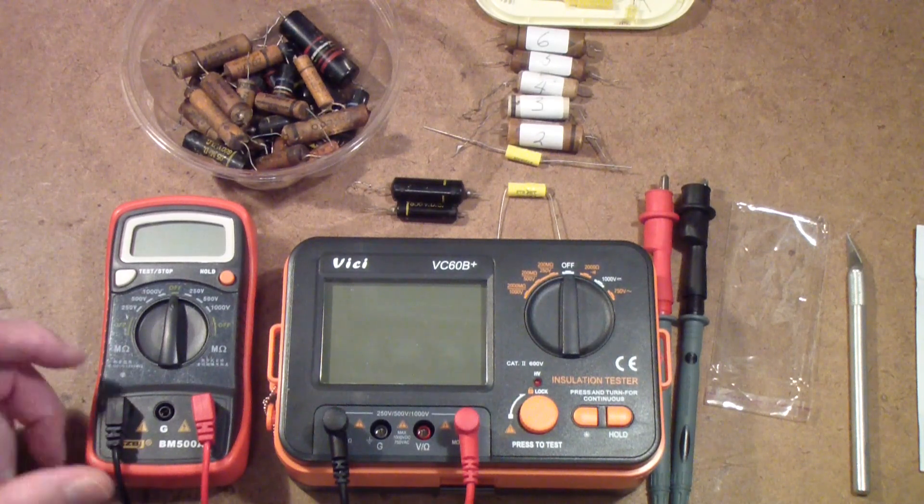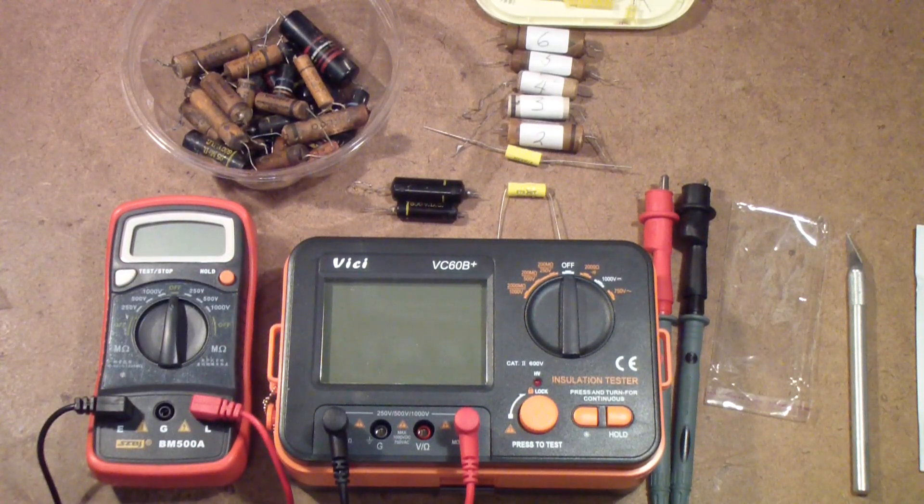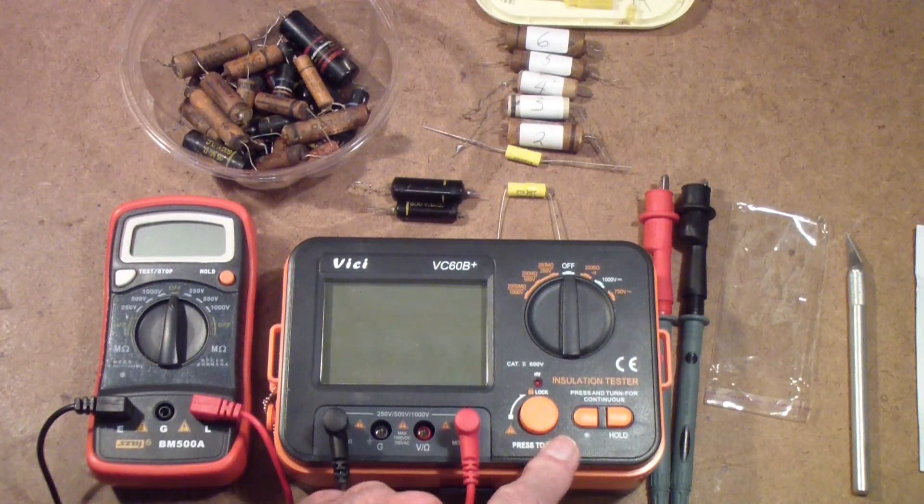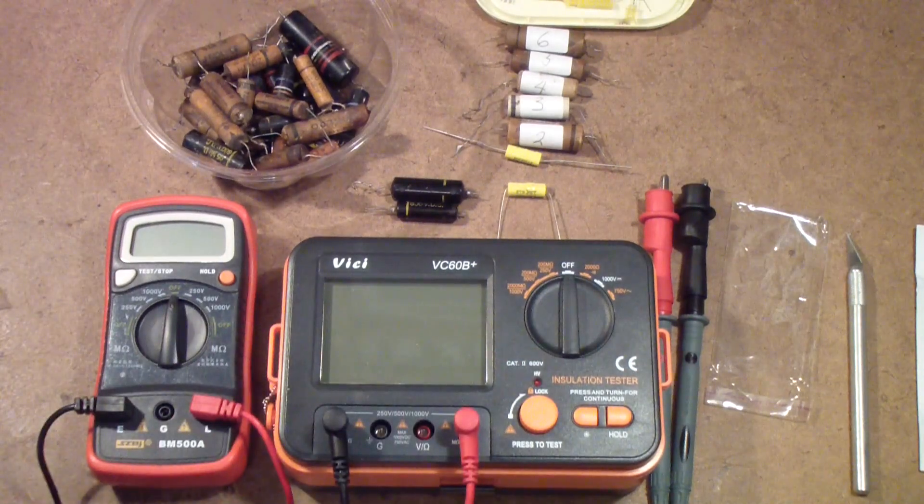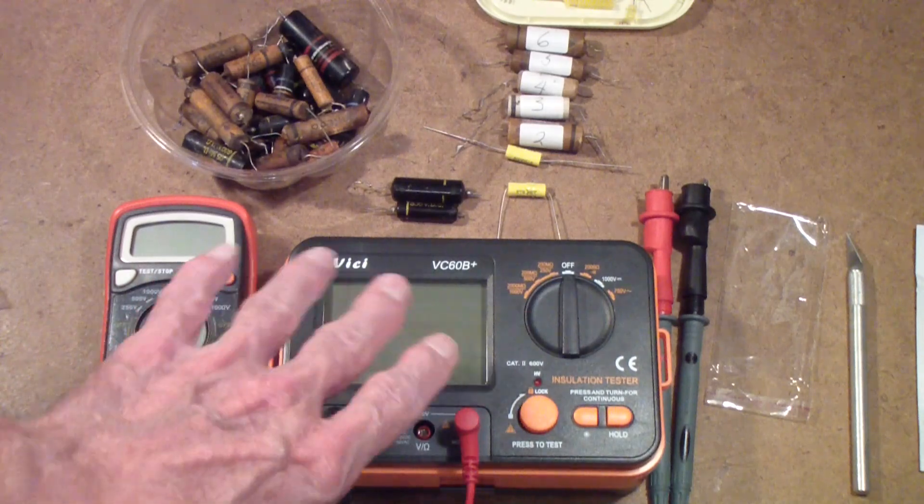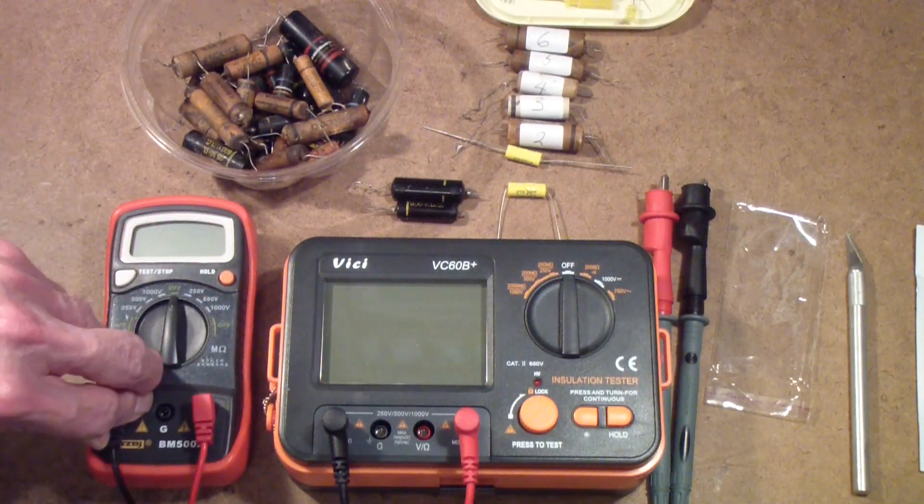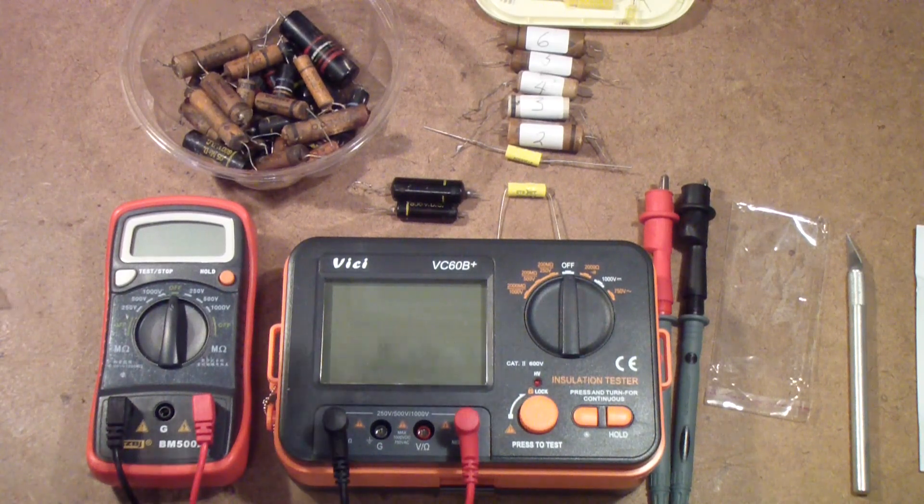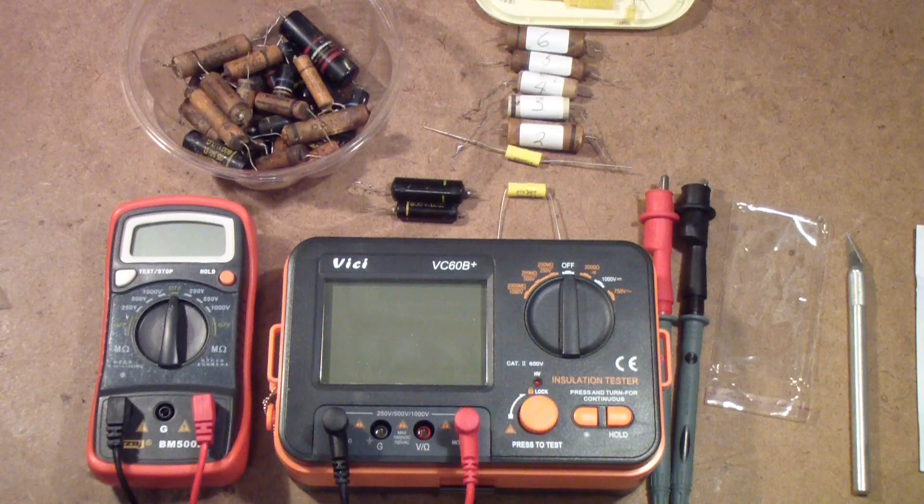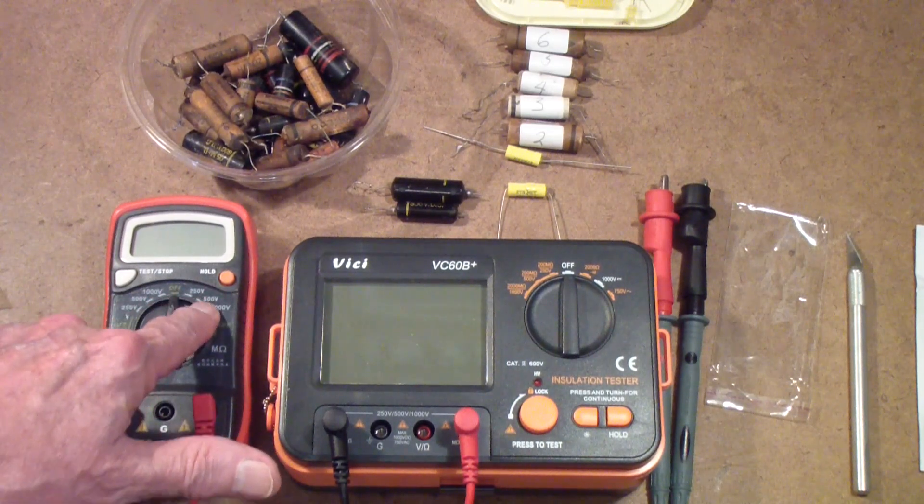This particular meter I don't know if it is CAT rated or not. The VC60B does say it is rated for CAT II 600 volts, but obviously you don't want to use these meters on service wiring that comes in from the street because you need a CAT IV meter for that. Everything I'm going to be using these for is inside an electronics lab and in every case there won't be any water, won't be any high humidity, won't be a lot of metal cases to worry about. So the differences between these is this one will measure up to 2,000 megaohms at 250, 500, or 1,000 volts.